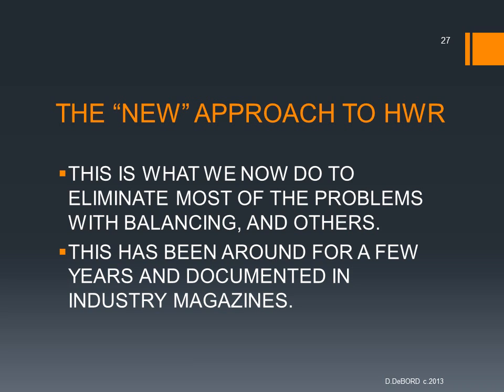But the main problem with that is that the one pump you have at the bottom of those zones is big, and it's usually going to be a base mounted pump, 3,500 RPMs. It's going to be noisy and have a lot of vibrations, and that's not conducive to a domestic residential environment. Businesses don't want to hear the noise either.